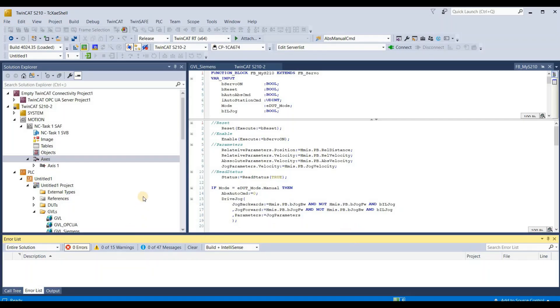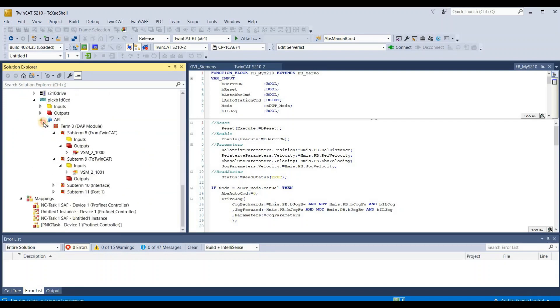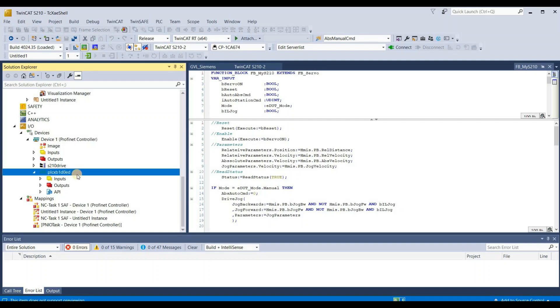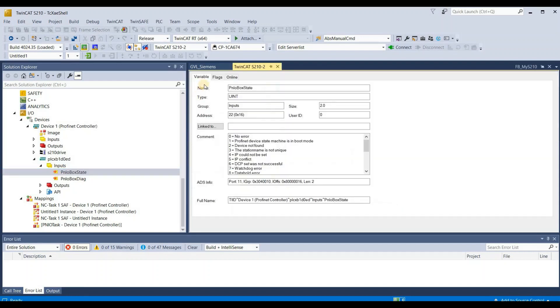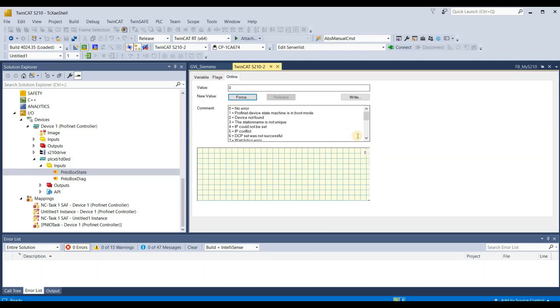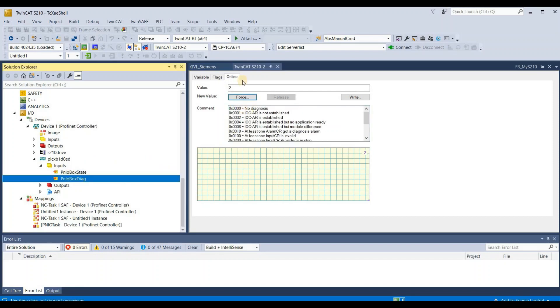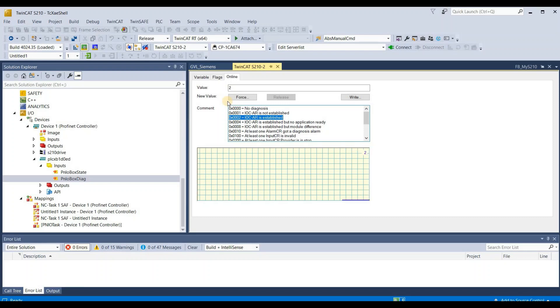We can also check on the TwinCAT side. Go to your Profinet device, go to Input, and check these two variables. Go online. You can see the value is 0, which means no error. And go to PNIO — you can see the value is 2, which means IOCAR is established, meaning communication is established without any error. Done.